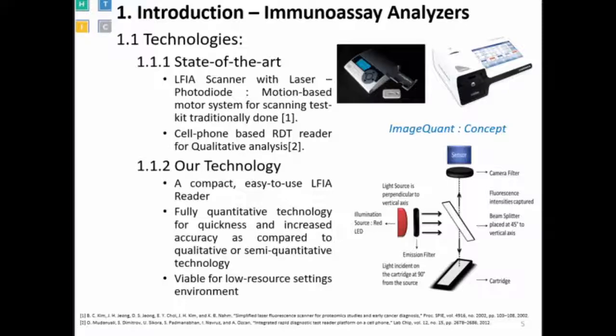As an introduction, I will give a brief about immunoanalyzers. State-of-the-art tabletop analyzers are mostly LFIA analyzers — lateral flow immunoassay. These lateral flow analyzers are usually laser and photodiode based. Each cartridge has test and control lines. You must have seen pregnancy kits — that is one form of lateral flow, but it is qualitative, giving an answer of yes or no. In many cases, you also need a quantitative answer.